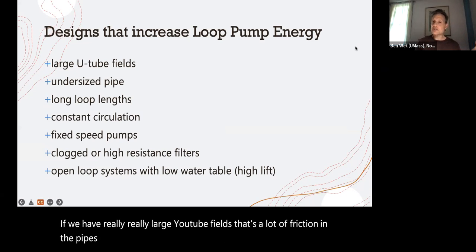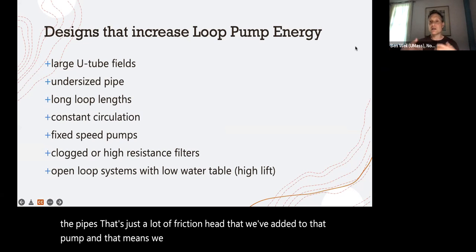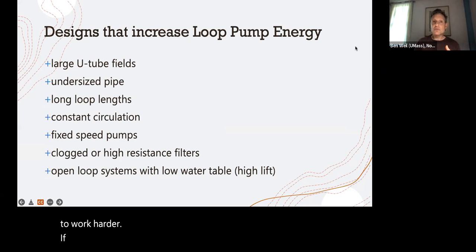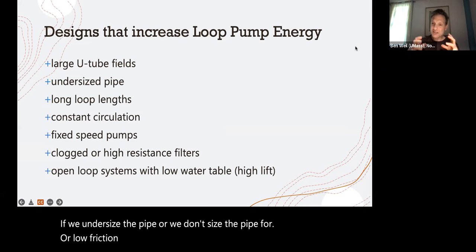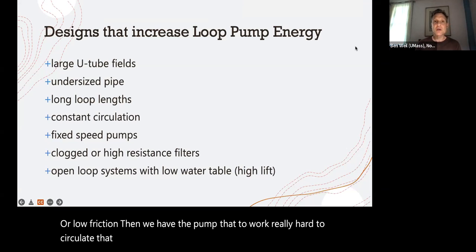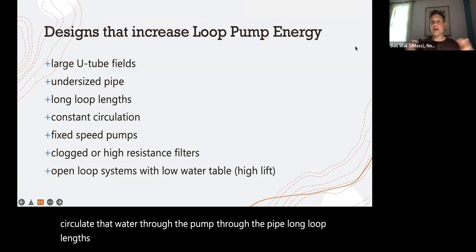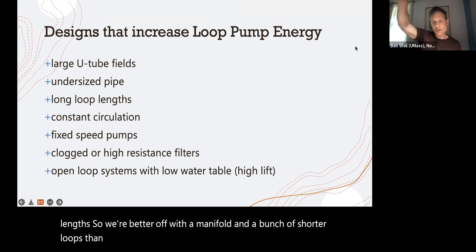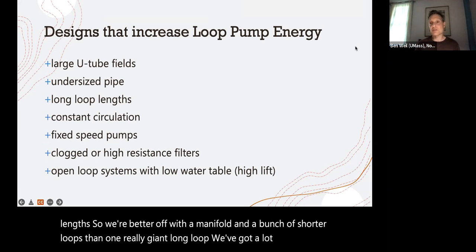That's just a lot of friction head that we've added to that pump. And that means we need a bigger pump and it's going to work harder. If we undersize the pipe, or we don't size the pipe for low friction, then we have a pump that has to work really hard to circulate that water through the pipe. Long loop lengths. So we're better off with a manifold and a bunch of shorter loops than one really giant long loop where we've got a lot of static pressure we've got to fight.